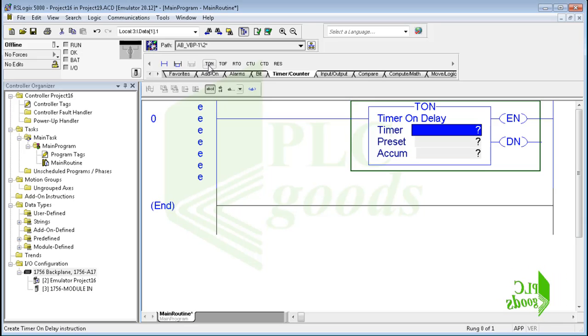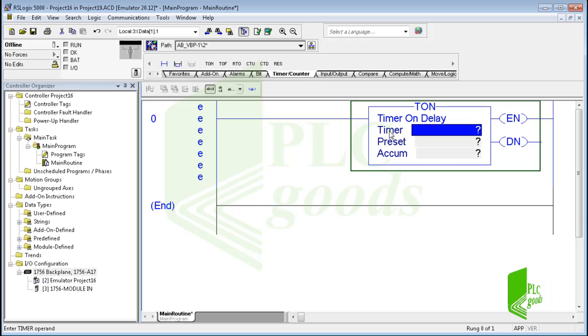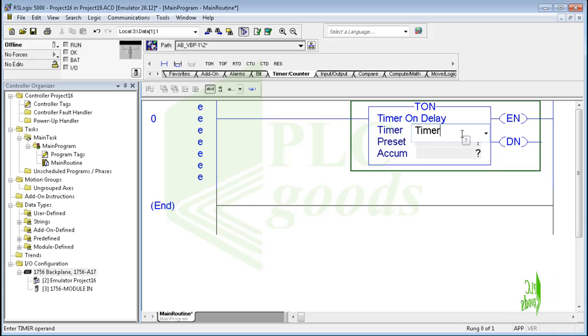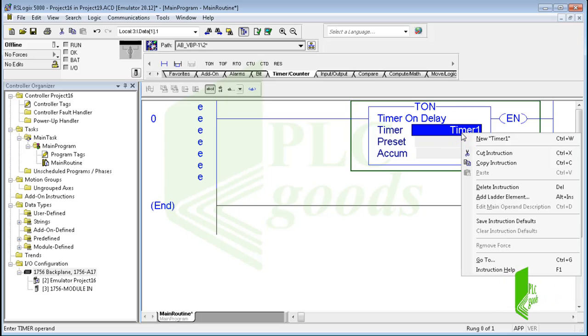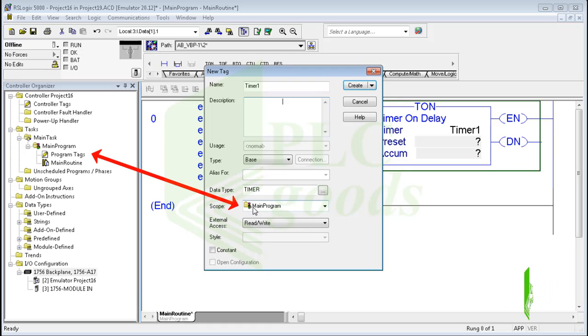The on delay timer is a non-retentive output instruction used when the application requires an action to occur at some time after the rung conditions for the timer become true. When we want to use a timer we must create a tag of type timer and enter the preset and the accumulated value. The tag must be defined before the preset and accumulated value can be entered. Let me right click on this tag and select new — here I can change my tag properties, its data type is timer.